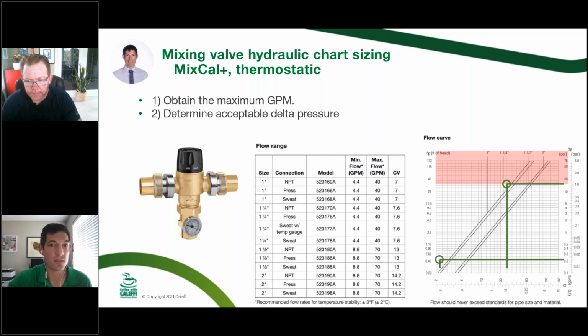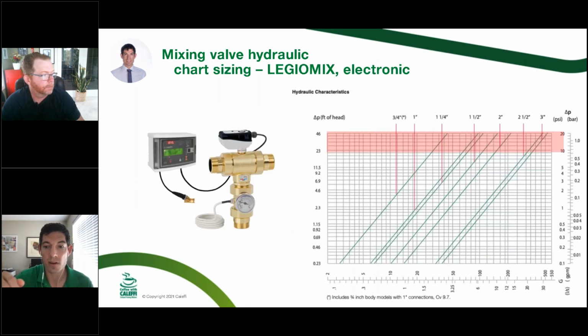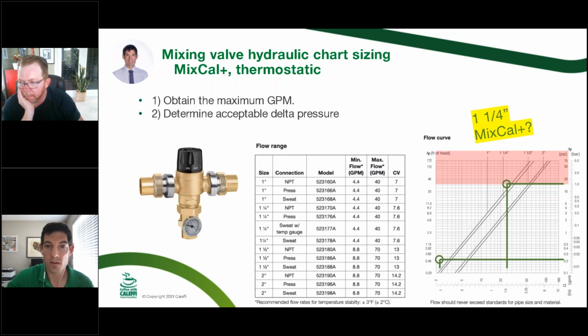That is closer, but we want to look at the chart and see what the actual delta P is for those conditions. So if we said that the flow conditions here are 2 to 30, you can kind of see where I put on the lines there in the green. So it looks like this is going to be a good fit for 1.25 inches, if you can see in more detail there. Oh, sorry. Back one more.